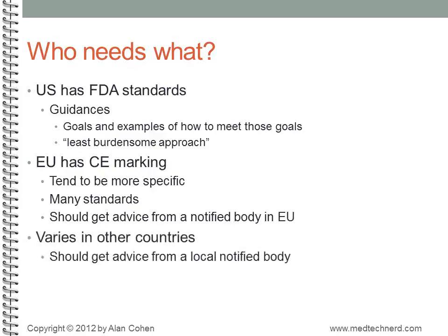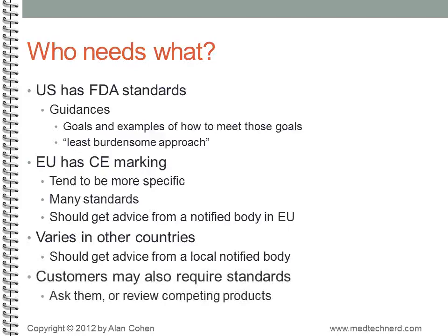Other parts of the world have other requirements. It's best to get advice on how to address these from a local notified body. And finally, customers may be looking for specific standards, even if the government does not require them. It's best to talk with prospective customers and to review the standards that are met by similar devices which are already sold in markets of interest.